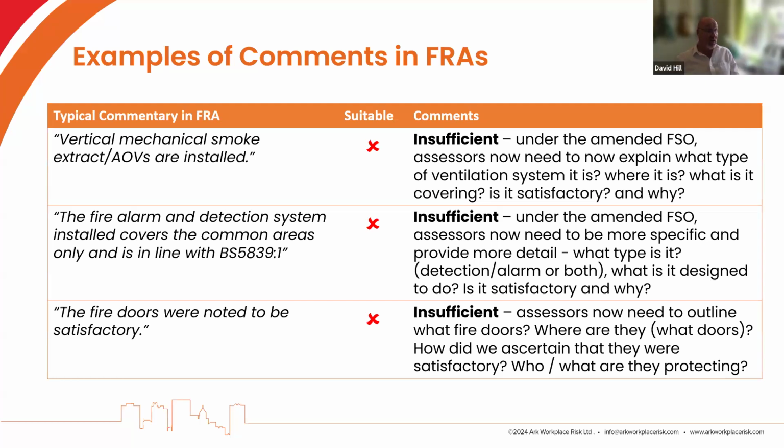And things such as fire doors were noted to be satisfactory. Well, that's, again, great. But we've also got to outline what fire doors, where are they? What are they doing? Who are they protecting? And why are they satisfactory? What evidence do we have to prove this? And at the end of the day, this is now all about proving what you are seeing as you undertake your fire risk assessment. Previously, it has been accepted that sometimes tick boxes with no commentary, or tick boxes with a little bit of commentary, are perfectly acceptable. That is not going to be acceptable for the vast majority of cases going forward. There has to be a greater degree of commentary. And that is what this is trying to achieve.